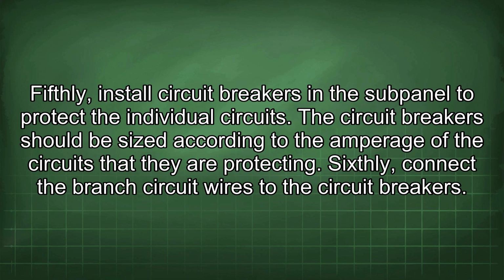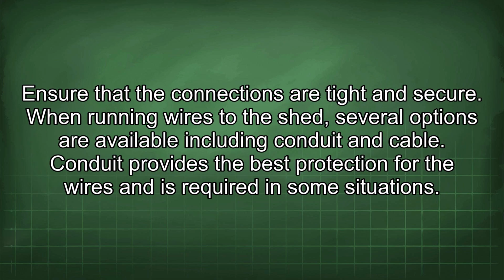Fifthly, install circuit breakers in the subpanel to protect the individual circuits. The circuit breakers should be sized according to the amperage of the circuits that they are protecting. Sixthly, connect the branch circuit wires to the circuit breakers. Ensure that the connections are tight and secure.